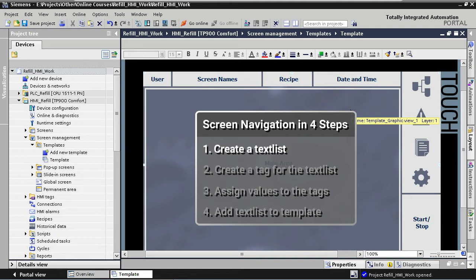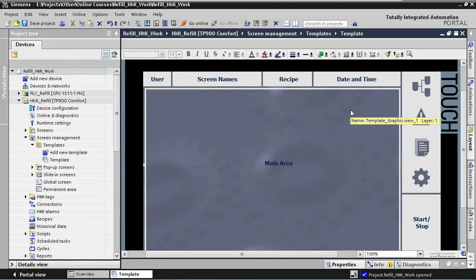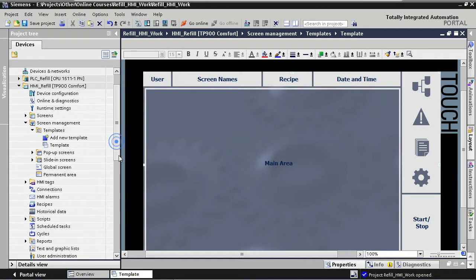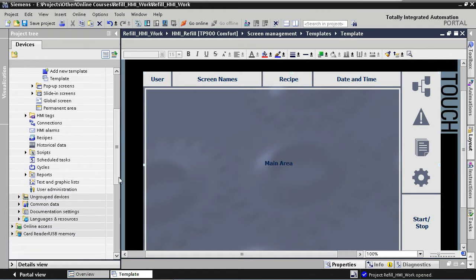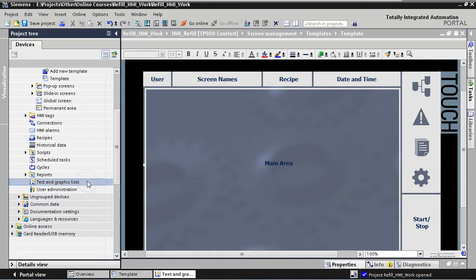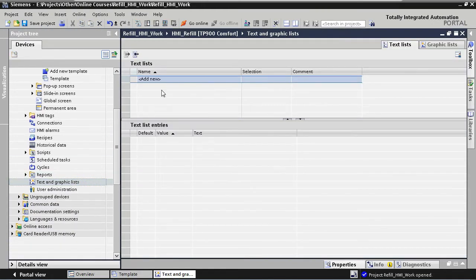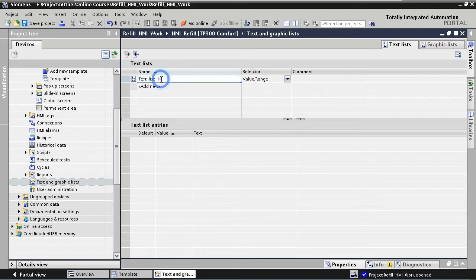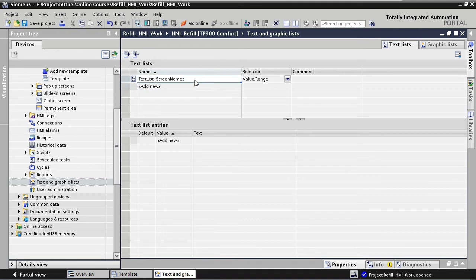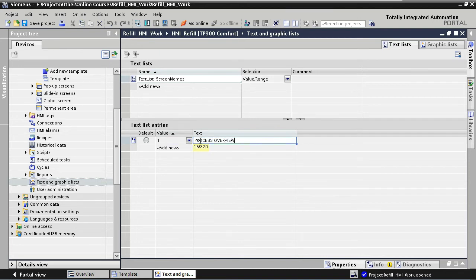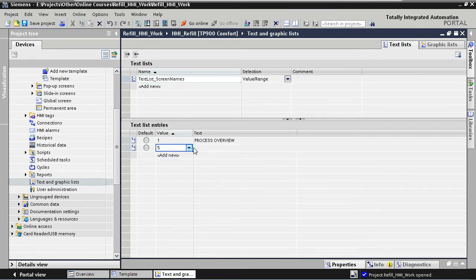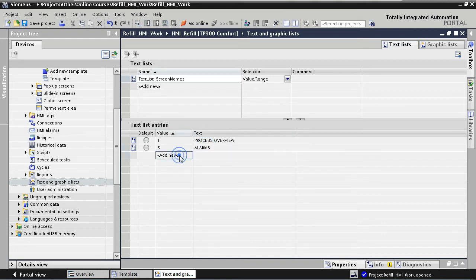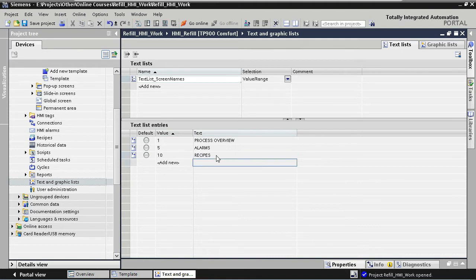So we start with our first step, creating a text list with the screen names. To create a new text list, we go to our tree structure on the left and we select text and graphic lists. Under text list, we create a new text list with the name text list screen names. If our tag has the value 1, we will show the text process overview. For the value 5, we will show alarms. For value 10, we show recipes. And for value 20, we show settings.